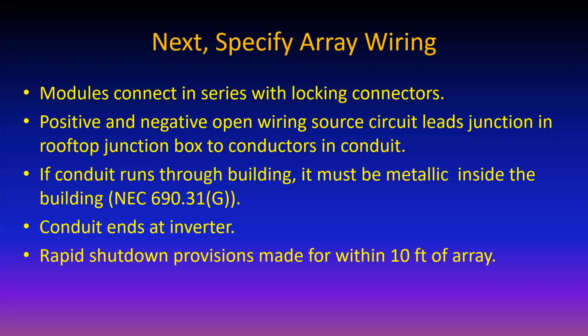And the nice thing is that the code is a performance specification as far as rapid shutdown. So it's up to the designer to decide what kind of rapid shutdown they're going to use. It just has to work. That's all. That's the requirement. And it has to work within about 2 feet of the array, I think, is the current requirement.